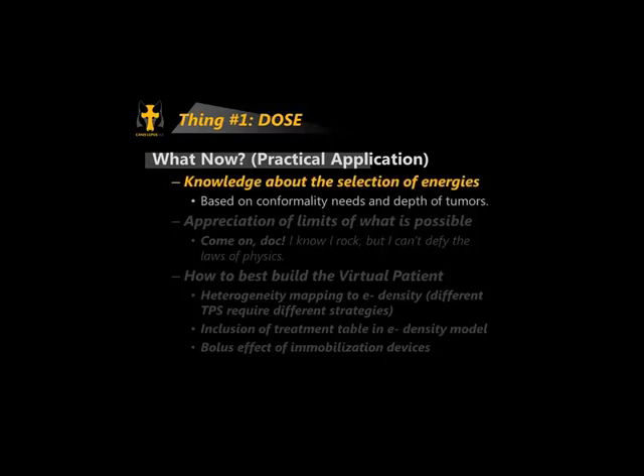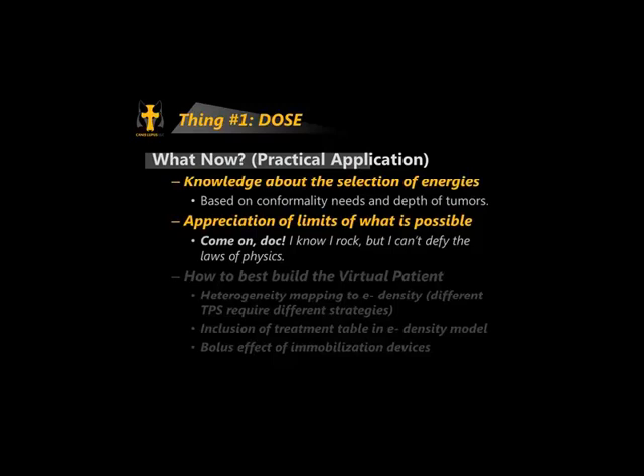Here's another interesting example — planned dose looked blurry, but actual delivery was crisper and cleaner. The DVH showed that in reality, targets and even critical structures did better than the treatment plan. How? This was a really bad energy spectrum and source model in the TPS, causing the TPS to think dose deposition was far too blurry. Again undetected by conventional dose QA because it was only in high-gradient regions. The treatment planner was stuck with this blurry model — making the plan inaccurate and planning more difficult.